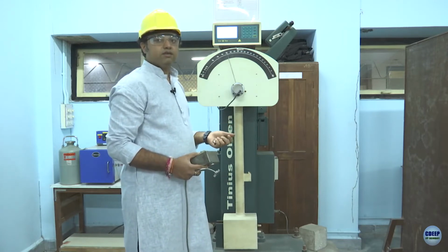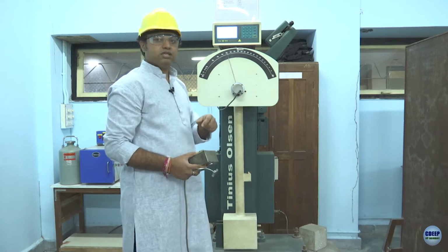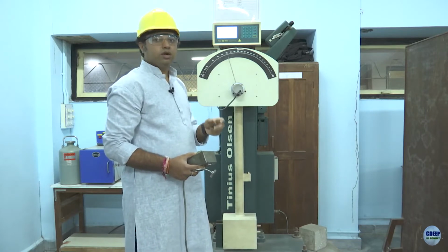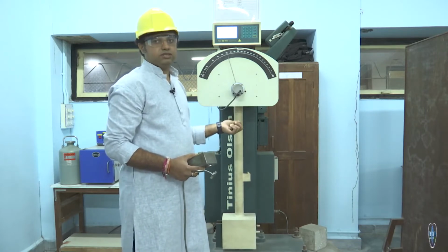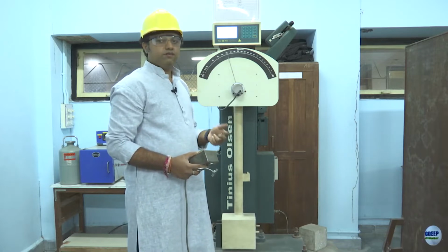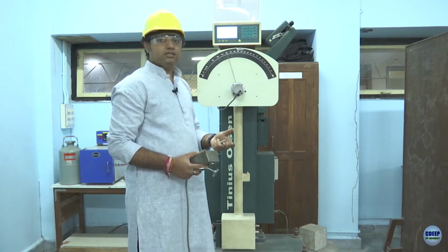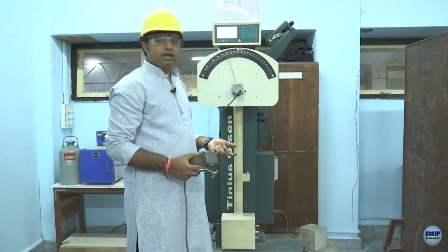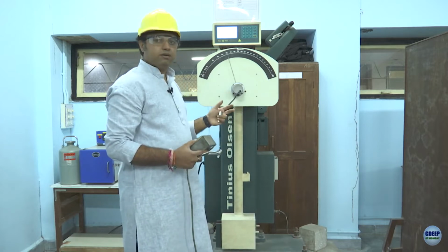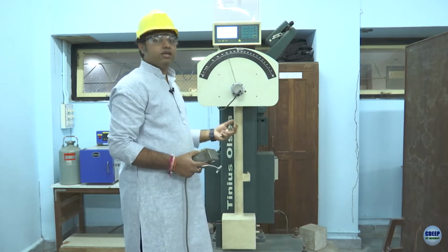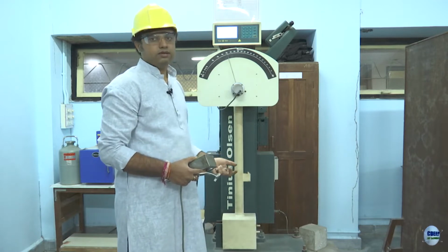The company has given us a range, like the calibration value can fall within 20% of the capacity of the machine. If the value doesn't fall in that range, then we need to calibrate again, or there might be some bigger issue that we need to solve.